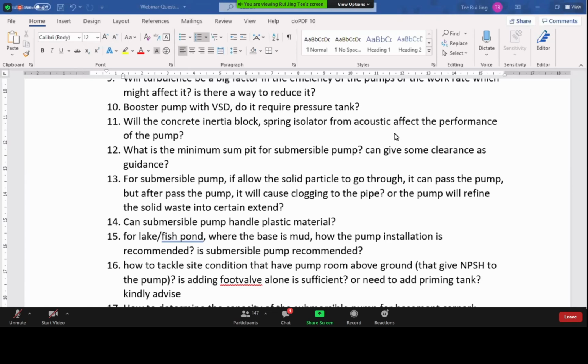In terms of sizing, usually we just follow the standard sizes. For a certain, let's say, small flow rate, we could use just a 24-liter tank. But if, let's say, the flow rate is above 30 or 40 cubic meters an hour, then we would use up to a 100-liter tank. So a bigger flow rate means we use a slightly bigger tank for that purpose. Yeah.